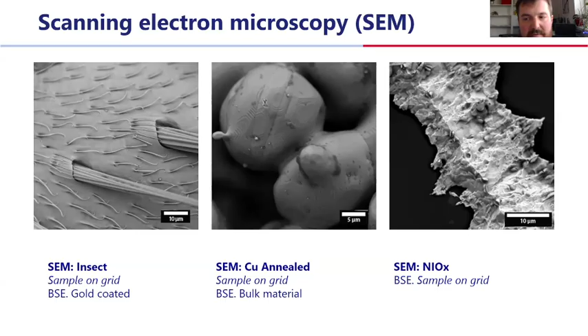There is also SEM mode in the dedicated TEM. SEM mode is especially useful for samples that are partly transparent and partly bulky, because it allows you to analyze all parts of the specimen in a complementary way. It can also be very effective for immunolabeling, for example, where metallic particles really stand out thanks to the strong material contrast provided by the backscatter electron detection. And even if SEM imaging is not your main focus and it's not the main mode of the microscope, it's simply convenient to have SEM capability available in the same instrument, ready to use whenever an SEM type sample appears.